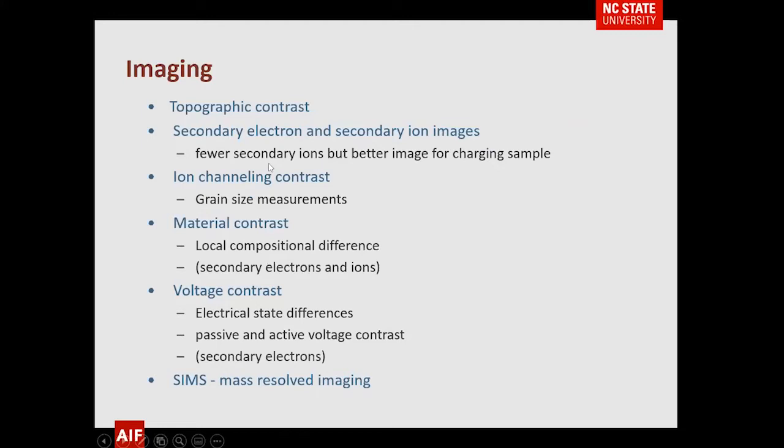For imaging, there are many different types of contrast: topography via secondary electrons, which is probably what you'll be most used to with the instrument; ion channeling; material contrast; voltage contrast; and secondary ion mass spectrometry. You can actually look at the positive and negative secondary ions and get information from them.